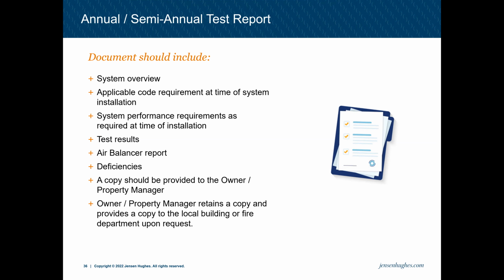We've seen some cases where, after a construction project is done as a renovation in a building, the smoke control system doesn't work. It might be flagged by the fire department. And if you don't ask for these reports ahead of time, it's very tough, if not impossible, to figure out if the project you might be associated with caused these systems to not work, and therefore you might be liable for making them work, or if the system never actually worked in the first place before your project started. If it didn't work, you can incorporate fixing and addressing this as part of your project, or show that it didn't work before your project happened, and therefore hopefully you aren't the ones that should be taking ownership of making the system work.